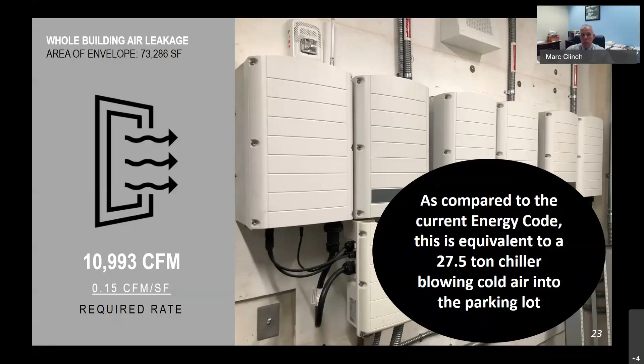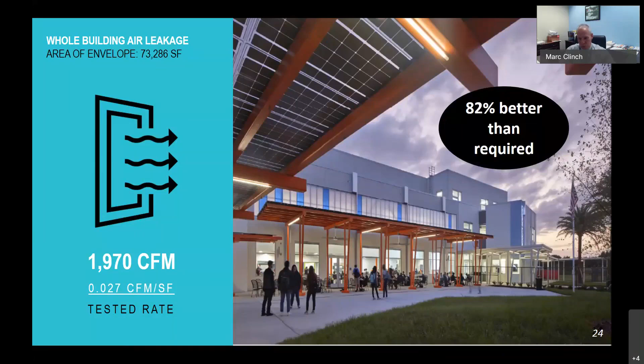So it just goes to show, this is a great example, that when you tighten that building envelope, you now have the opportunity to right size, to downsize your mechanical systems. So what we actually achieved was an air leakage testing of 0.027, 82% better than the criteria, that 0.15 cubic foot per minute per square foot that we had set for the project. Less than 2,000 cubic feet per minute. And again, ladies and gentlemen, this is very achievable. It requires attention to detail, but it starts with shifting that paradigm with your designers and construction managers.